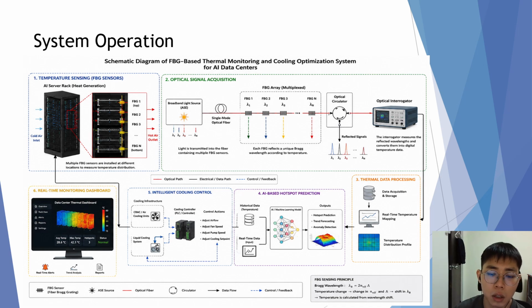Next, the intelligent cooling control system. The cooling management system receives control signals generated by the AI prediction module depending on the thermal condition of the AI data center. It dynamically adjusts cooling resources, such as CRAC units or liquid cooling systems, to maintain the optimal operating temperature while minimizing unnecessary energy consumption.